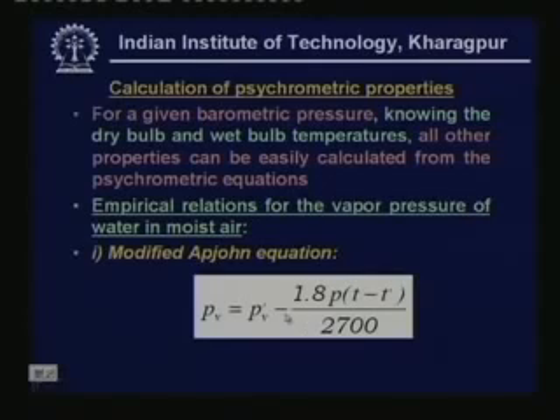So first let us look at calculation of psychrometric properties. As I have already mentioned, using a psychrometer one can measure both the dry bulb and wet bulb temperatures, and one can also measure the barometric pressure, for example using a barometer. So once we know the barometric pressure and the dry bulb and wet bulb temperatures, how do we find the rest of the properties? The first task is to find the vapor pressure. The vapor pressure can be obtained by using any of the empirical relations shown below.